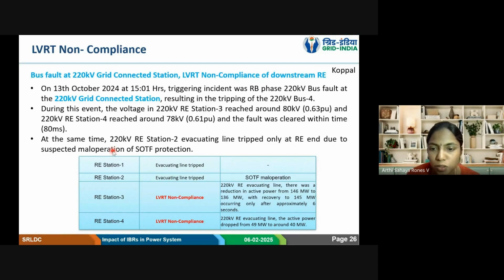Next is also an LVRT related non-compliance. In this case, there were multiple RE stations connected to one pooling station, and that pooling station is connected to the grid. There was a fault in the pooling station. This happened in Karnataka, and in that pooling station, only one bus section was faulty, which was connected to RE station 1. The tripping of that line is in order because the bus bar protection operated and the line connected to that bus section got tripped.